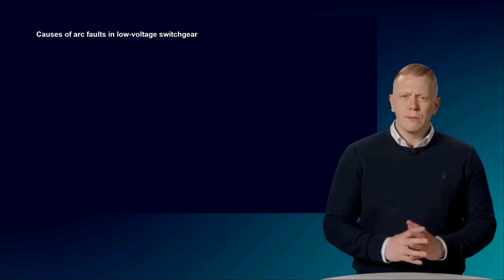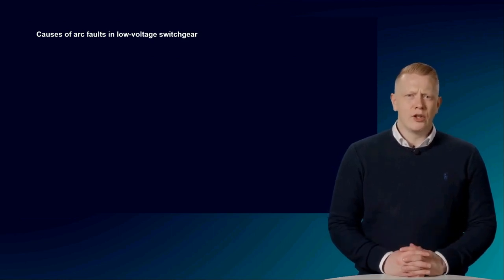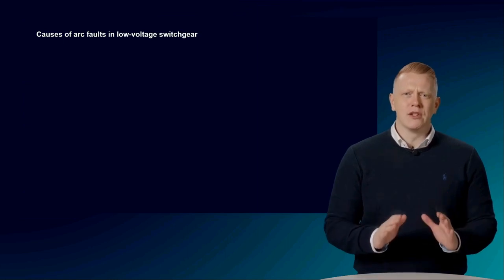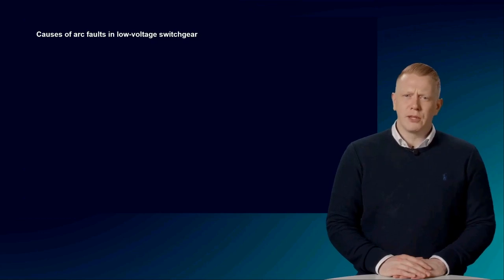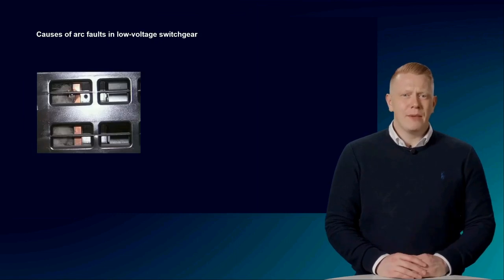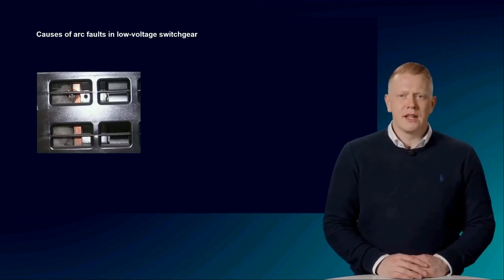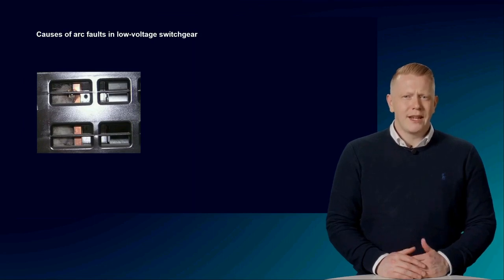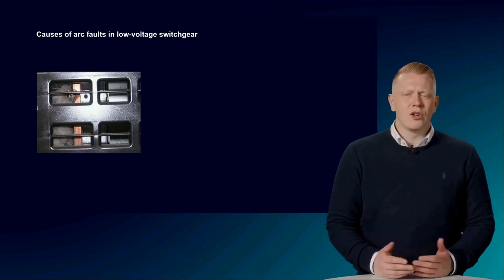It is important to know how such incidents can occur. Arc faults are very rare — they represent an absolutely exceptional situation. In practice, we see a wide range of possible causes. On one hand, these can be external circumstances such as pollution, which means the insulation properties in the switchboard are no longer guaranteed. This can also be caused by animals that enter the system and cause a short circuit.